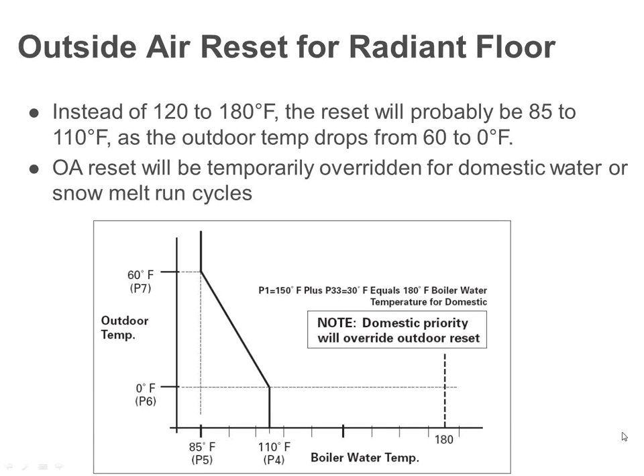So radiant floor systems, if you're not putting in a high efficiency boiler and you're doing it correctly, you're actually going to cost yourself more money, because you need some type of mixing devices, controls, and other things to add to that non-condensing boiler so it deals with its stated lowest temperatures that it can run at and not void the manufacturer's warranty. You can't run a cast iron boiler at radiant floor temperatures. You will definitely kill that boiler in a matter of years because it will be condensing and it's not designed to condense. So radiant floors, you should have condensing boilers if you're really doing your customer justice.